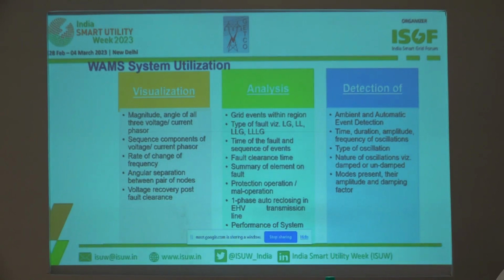Based on this data, we have replaced 2 or 3 CVTs by knowing the voltage profile of their particular 400 kV location. So we have saved those lines from tripping.